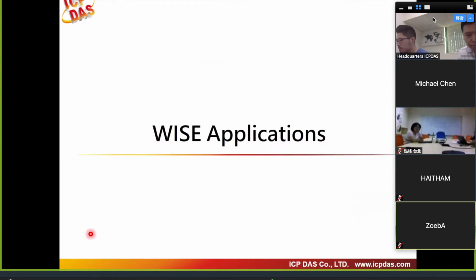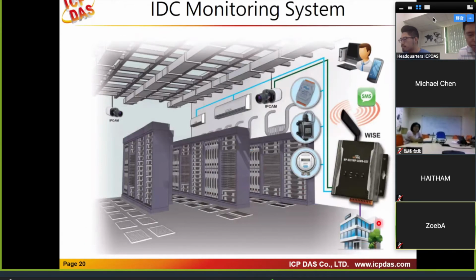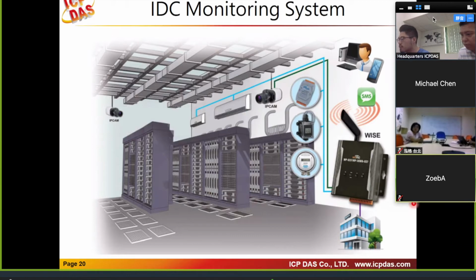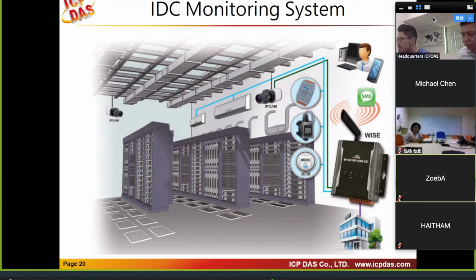So let's talk about the WISE applications that we use in the field. The first one I'd like to talk about is the IDC monitoring system. WISE can be used for monitoring the light-out control room, and WISE allows connection with ICP DAS I-7000 and Modbus RTU slave modules. Therefore, it's able to connect with the thermometer, hygrometer, air conditioner, warning devices, and access control system. Logic and daily regular maintenance in the control room can be set on WISE, and you can also connect your IP camera as well.